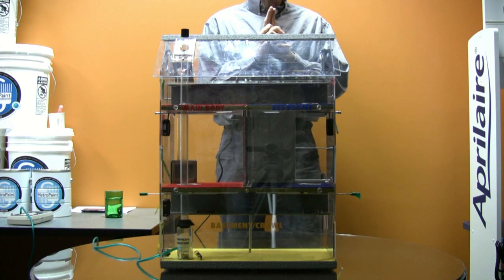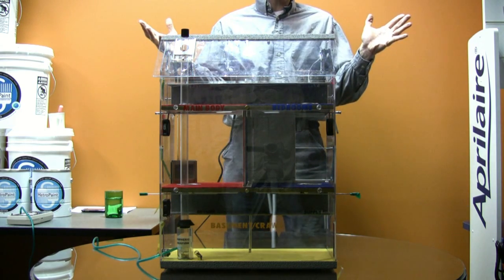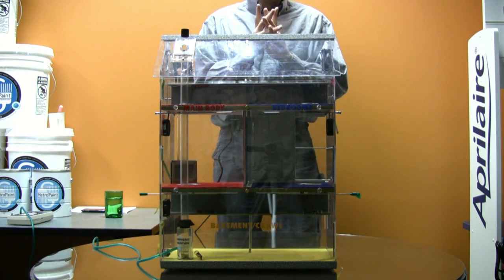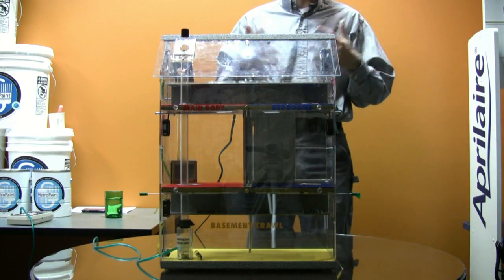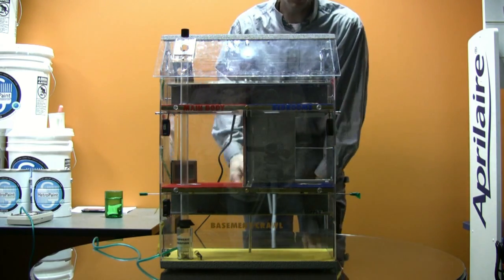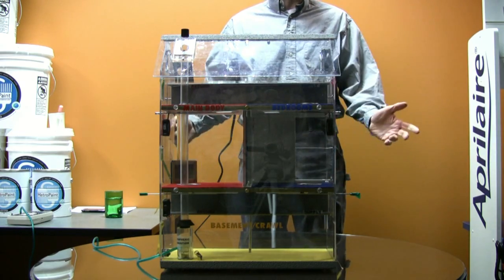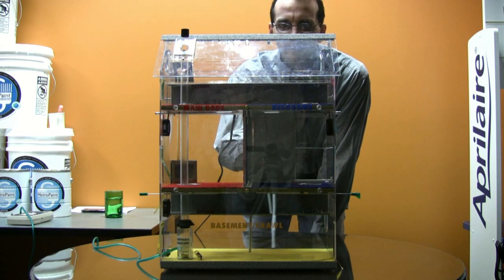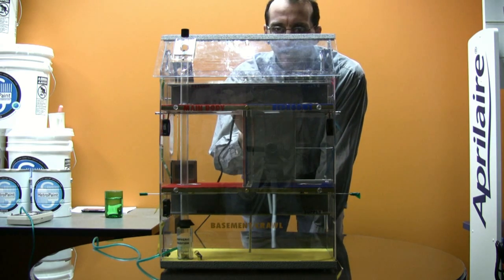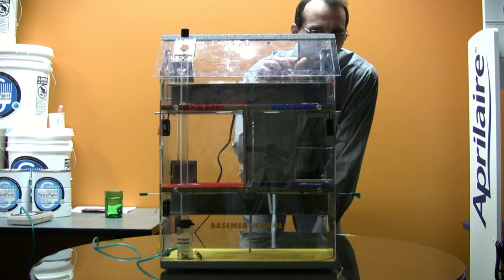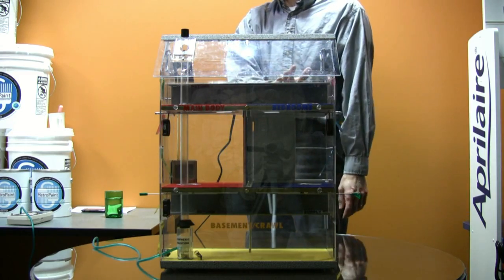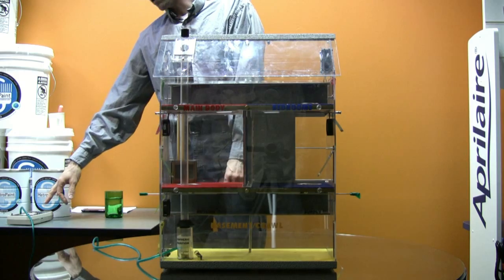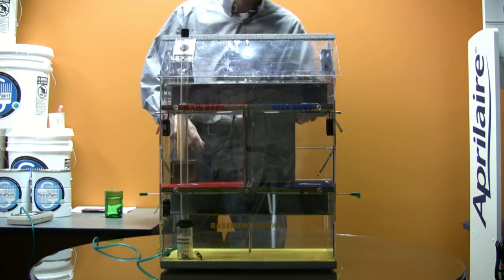Well, what are things that depressurize houses? Fans. So you turn on a bathroom fan on the second floor. A standard procedure, if you're following Building Performance Institute standards, is to go around and turn all the exhaust fans in the house on. So I'm turning on a bedroom exhaust fan and a main exhaust fan.